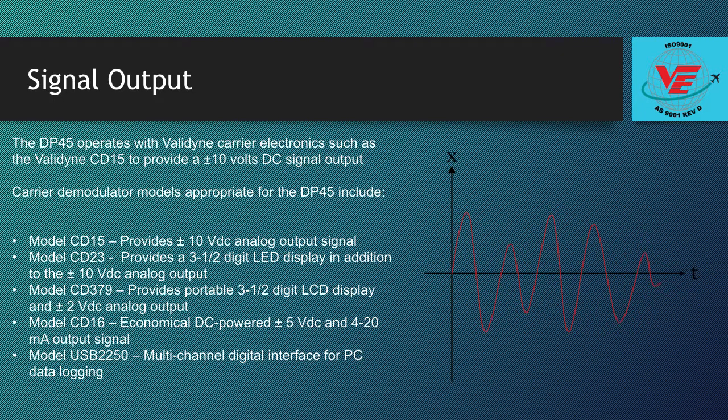The DP45 typically operates with Validyne carrier electronics such as the Validyne CD15 to provide a plus or minus 10 volts DC signal output. Validyne offers a wide variety of companion carrier demodulator electronics that also provide plus or minus 5 VDC, 4 to 20 mA, or digital pressure readings.